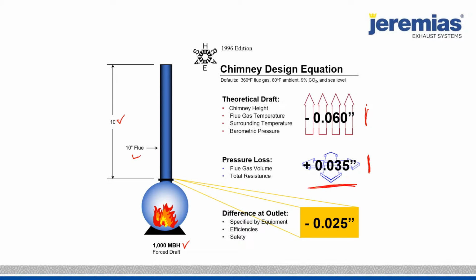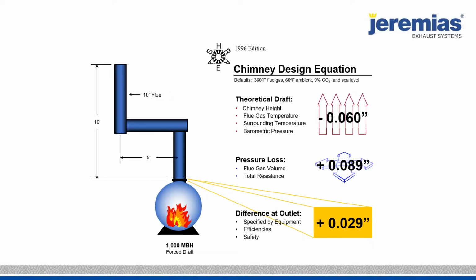And you do the math, negative 0.06 plus 0.035 is a negative 0.02. That's what you would measure at the outlet of the heater. Now, when we get into theory, we talk about the priming period. I mean, you don't get that negative 0.02 until like a couple seconds after, but a complicated system could be minutes after startup. So we have a negative 0.02 on this one.